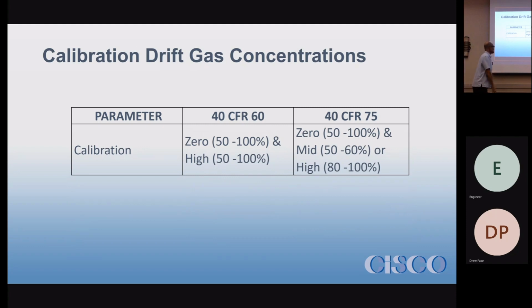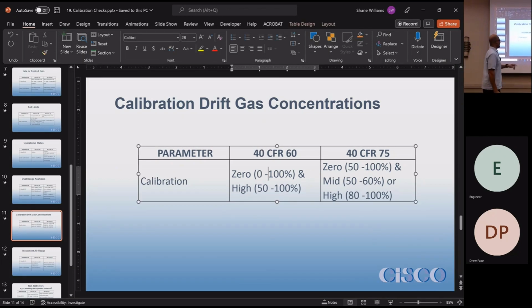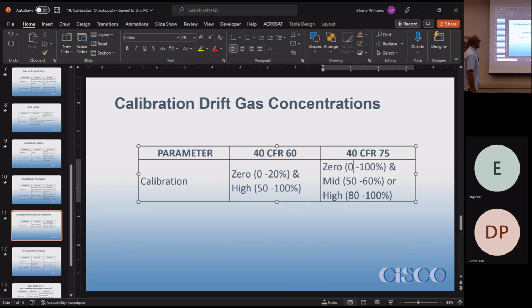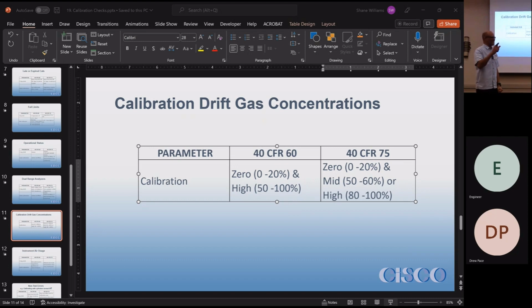Calibration drift gas concentrations, both. So for Part 60, the calibration limits, you have the range of 50 to 100% for daily calibration. So sometimes when you find yourself running short on gas, if your mid-range gas for your CGAs works, you can use that. Part 75 gives you the notice that, ooh, that 0 is not the right 0. It should be 0 to 20. Wow, I did it twice. I'm consistent.